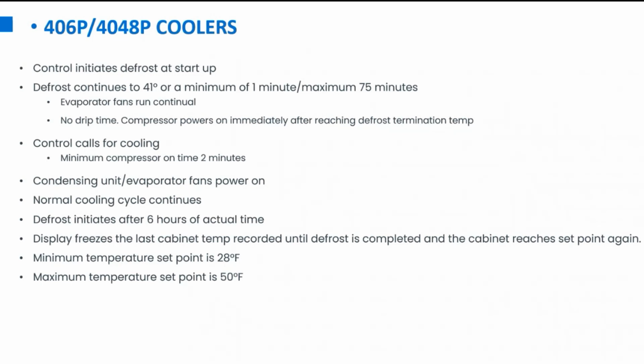But you see the cabinet temperature is dropping, but your display temp remains at ambient temperatures. That is something, again, you just want to keep in mind. When you initiate a defrost, that last known temperature, regardless of what that temperature is, will remain on that display until the defrost cycle and the next cooling cycle has satisfied. Once that next cooling cycle satisfies, that is when you will start to see the actual cabinet temperature being reflected on the screen.